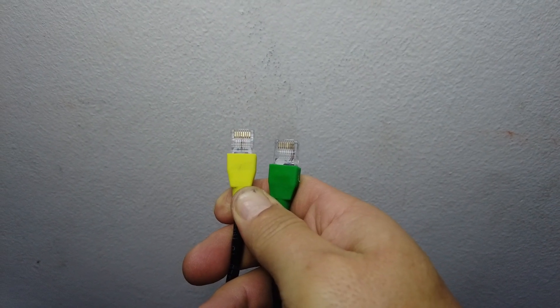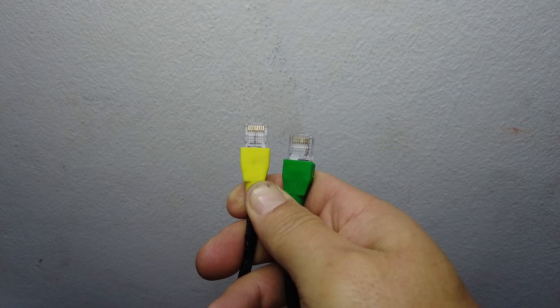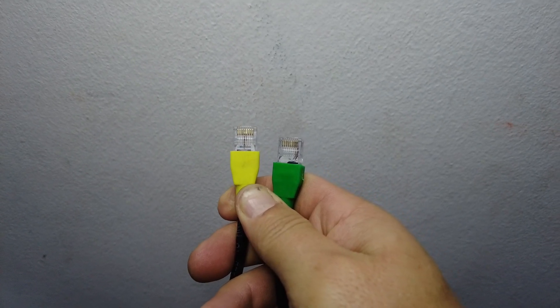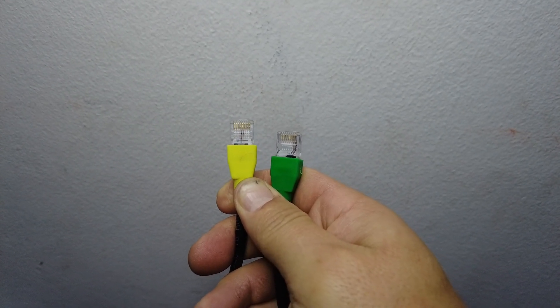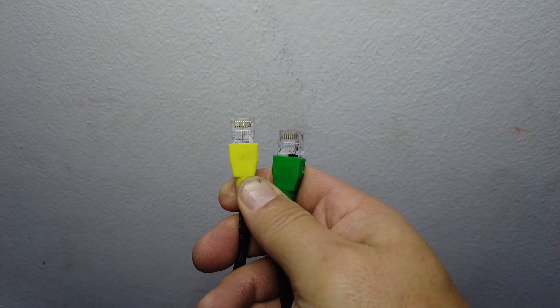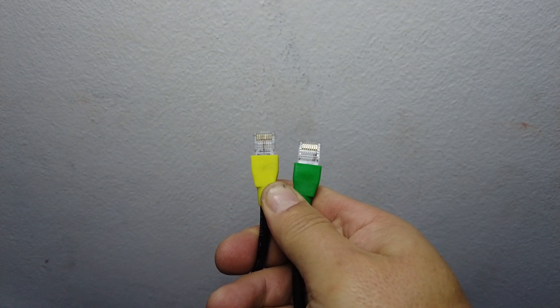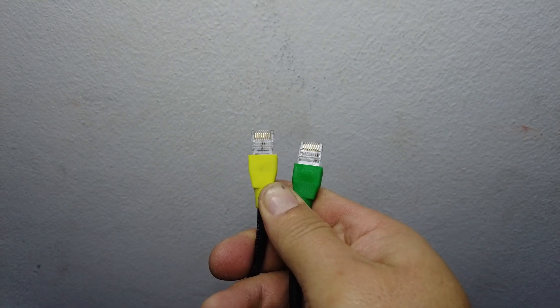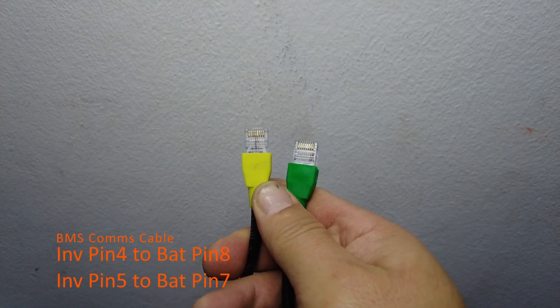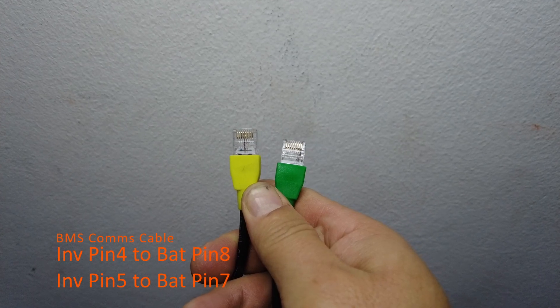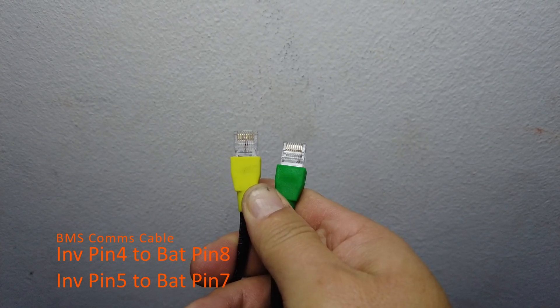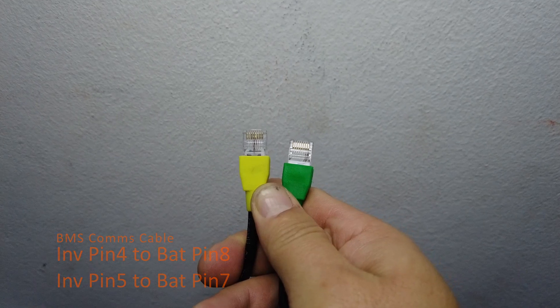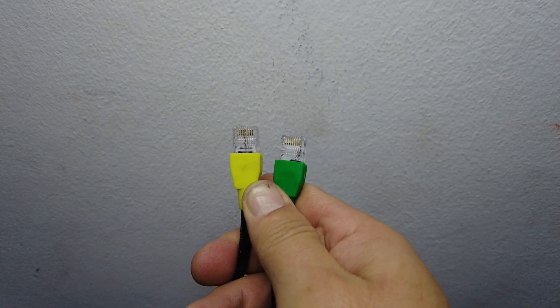For the BMS cable, the networking cable between the inverter and the battery, I've crimped the yellow one as the inverter side and the green one as the battery side. Inverter side pin number four will go to battery side pin number eight, and inverter side pin number five will go to battery side pin number seven.